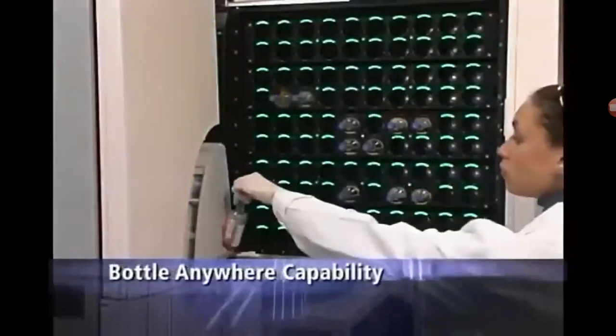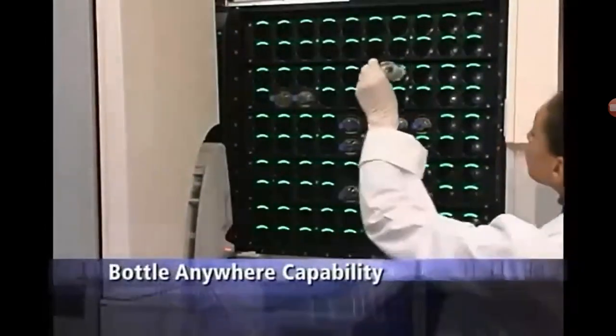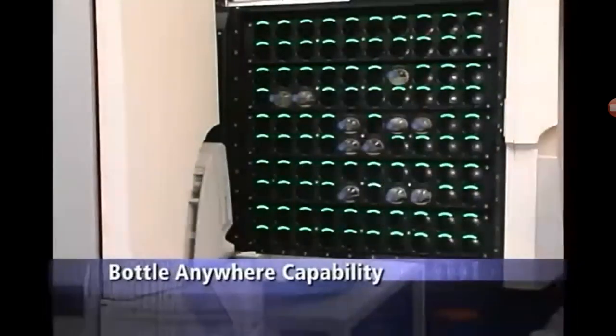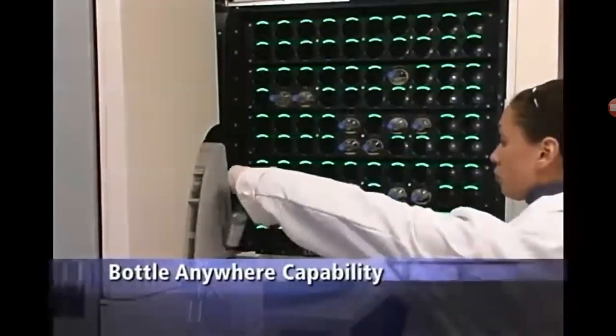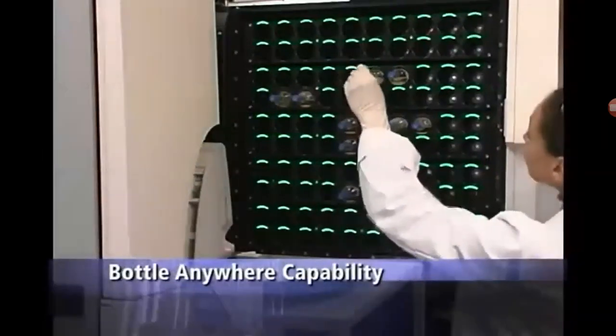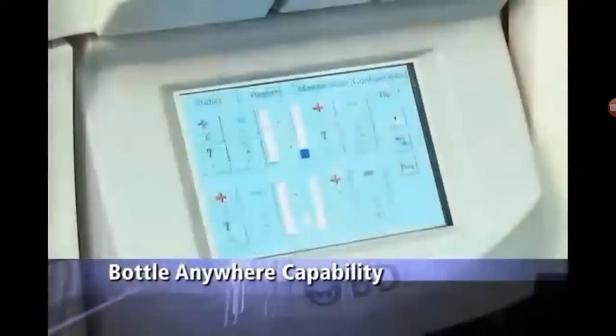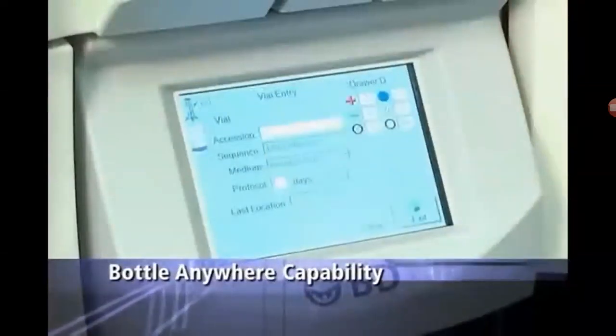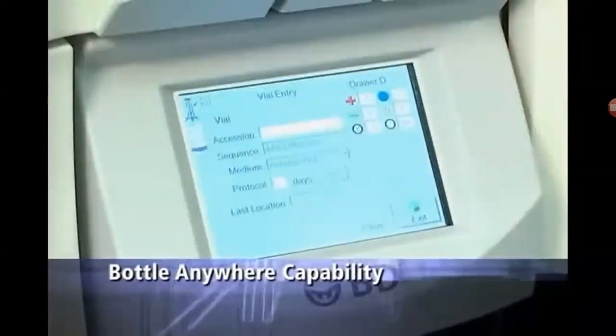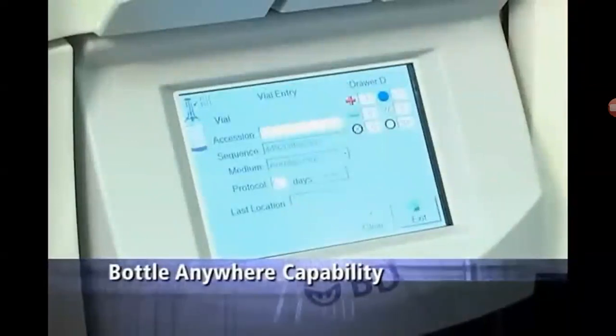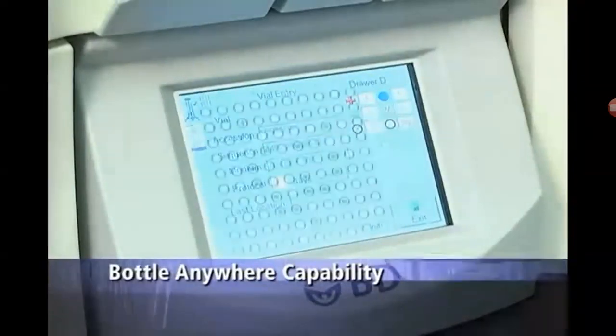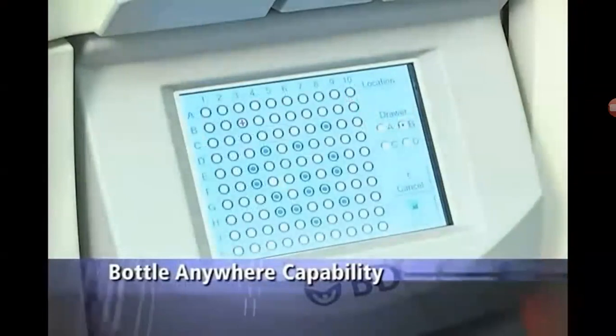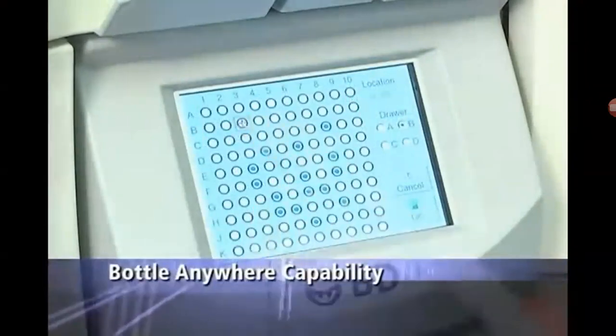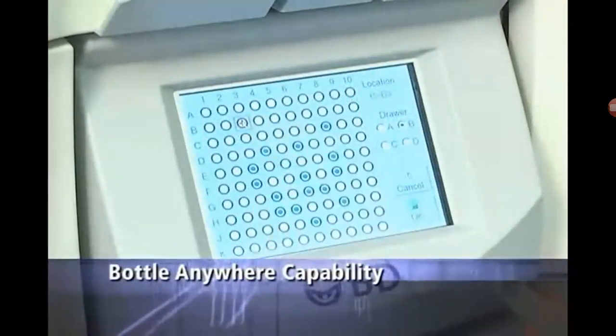For example, when entering your new culture vials, simply open the drawer, scan the new vial barcode, and place the vial in any available or open location as indicated by the steady green light. You decide where. The BACTEC FX instrument now automatically knows you're entering new vials and brings up the LCD workflow screen for vial entry, all without a keystroke. Sensors in the station know when and precisely where the vial is placed. Those same sensors can verify whether a vial is fully seated in the station and not inadvertently inserted partway. It's all part of the safety we have built into the system.